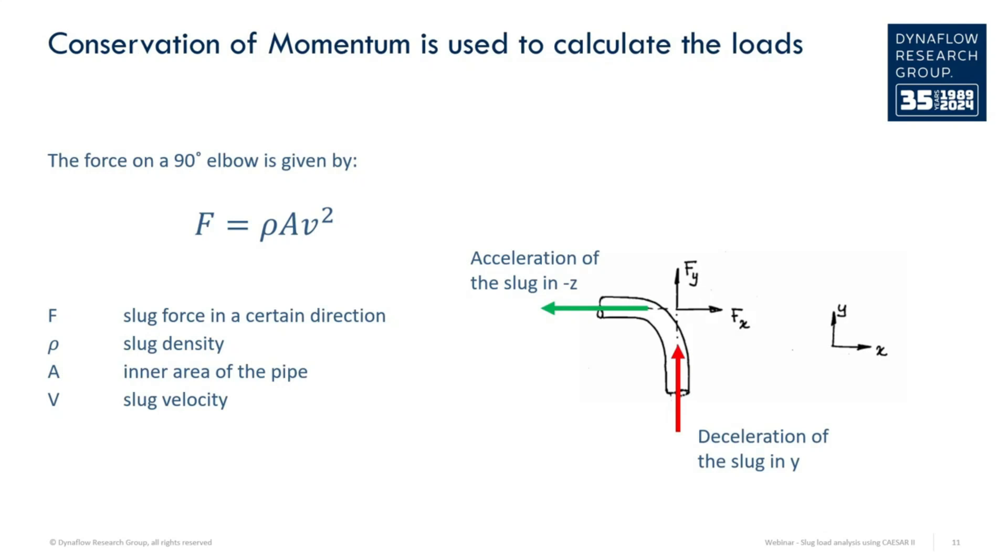Using the conservation of momentum, the slug force can be computed. The force on the elbow is caused by the momentum of the mass that is decelerated in one direction. This momentum is influenced by the velocity, the density, and the area.